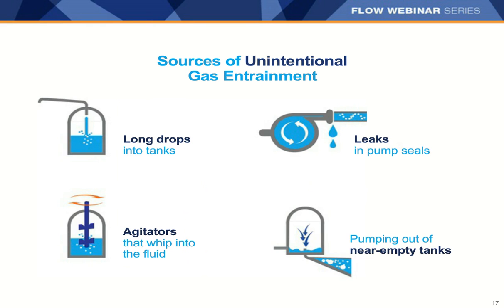Sources of unintentional gas entrainment include: long drops into tanks — the farther the liquid falls, the more air is entrained, and since tanks aren't see-through it's hard to know the drop distance; leaks in pump seals, which introduce entrained gas into the process; agitators that produce a vortex, entraining air — the vortex size and entrained gas increase as fluid level decreases; and pumping out of a near-empty tank, which sucks air into the process.